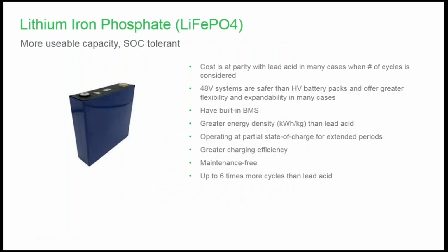So lithium iron phosphate is, I would say, overtaking lead acid, at least in the number of applications that I see. For the most part, they are specifying lithium iron phosphate batteries probably 3 or 4 to 1 at this point in time. So gradually they're gaining more and more popularity. In some cases, the cost is at parity with lead acid if you consider the number of cycles. You might replace a lead acid battery up to 3 times in the lifespan of a single lithium iron phosphate bank.